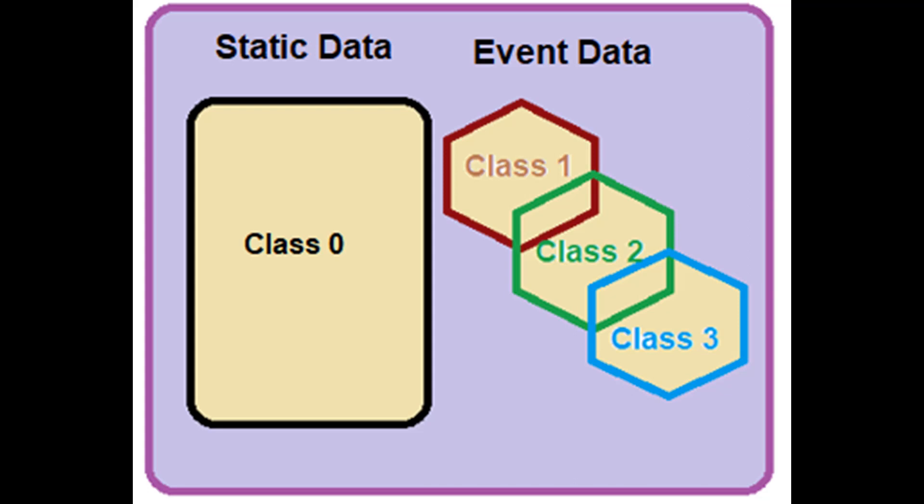DNP3 supports four classes: zero, one, two, and three. Class zero is the static class; classes one, two, and three are event classes. A master may ask for input data based on class — in fact, this is the most common way of getting data from an outstation. All static object groups belong to class zero, so a master can get the static value of all points by reading class zero. Each object that can report events is assigned to class one, two, or three. The master can get all events by issuing a single read for classes one, two, and three. More details will be presented in future lessons.